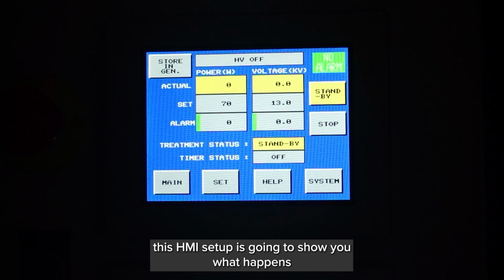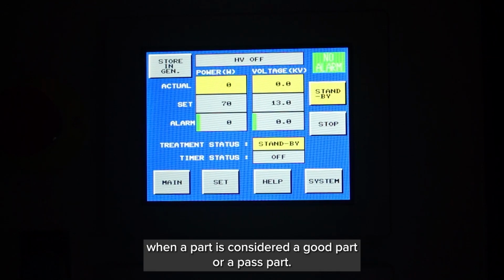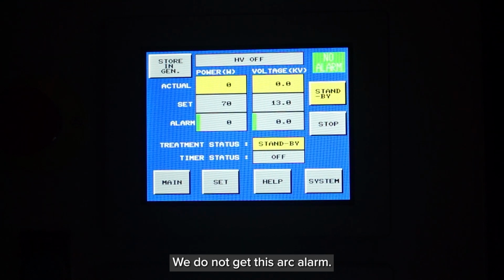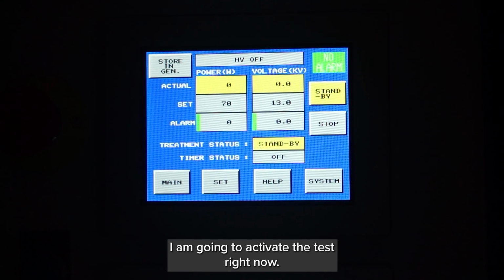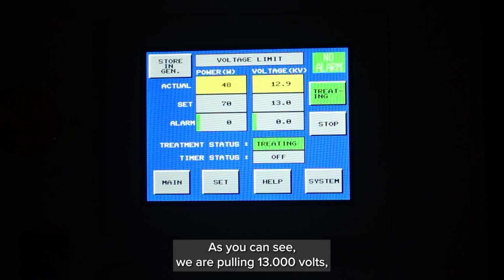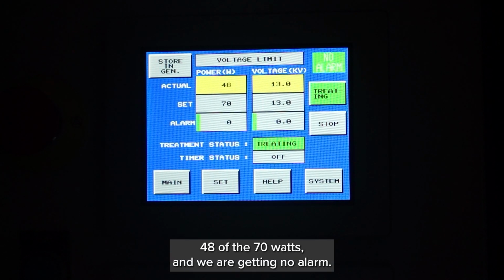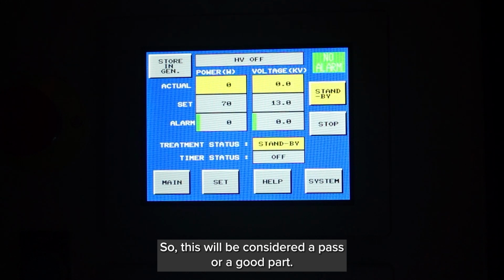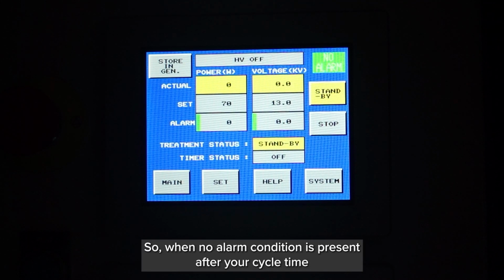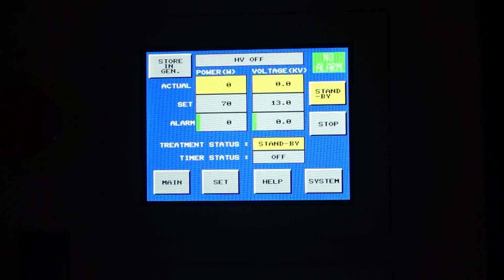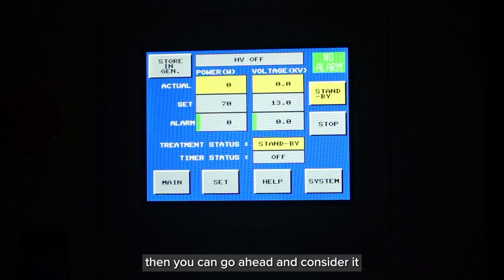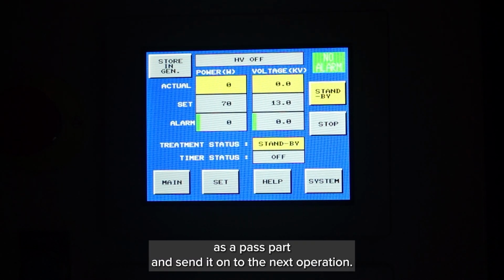Now this HMI setup is going to show you what happens when a part is considered a good part or a pass part, meaning that we don't get this arc alarm. I'm going to activate the test right now. As you can see, we're pulling 13,000 volts, 48 of the 70 watts, and we're getting no alarm. So this would be considered a pass or a good part. So when no alarm condition is present after your cycle time of the test has run, then you can go ahead and consider this a pass part and send it on to its next operation.